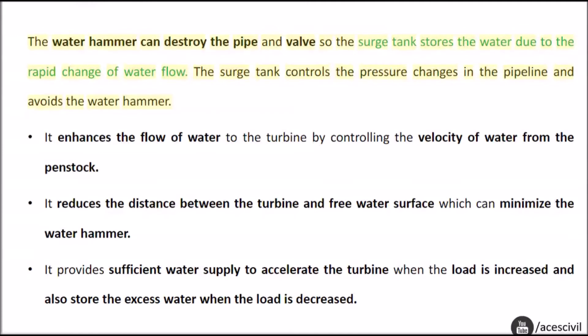The surge tank controls the pressure changes in the pipeline and avoids the water hammer. It enhances the flow of water to the turbine by controlling the velocity of water from the penstock. It reduces the distance between the turbine and free water surface, which can minimize the water hammer. It provides sufficient water supply to accelerate the turbine when the load is increased, and also stores the excess water when the load is decreased.